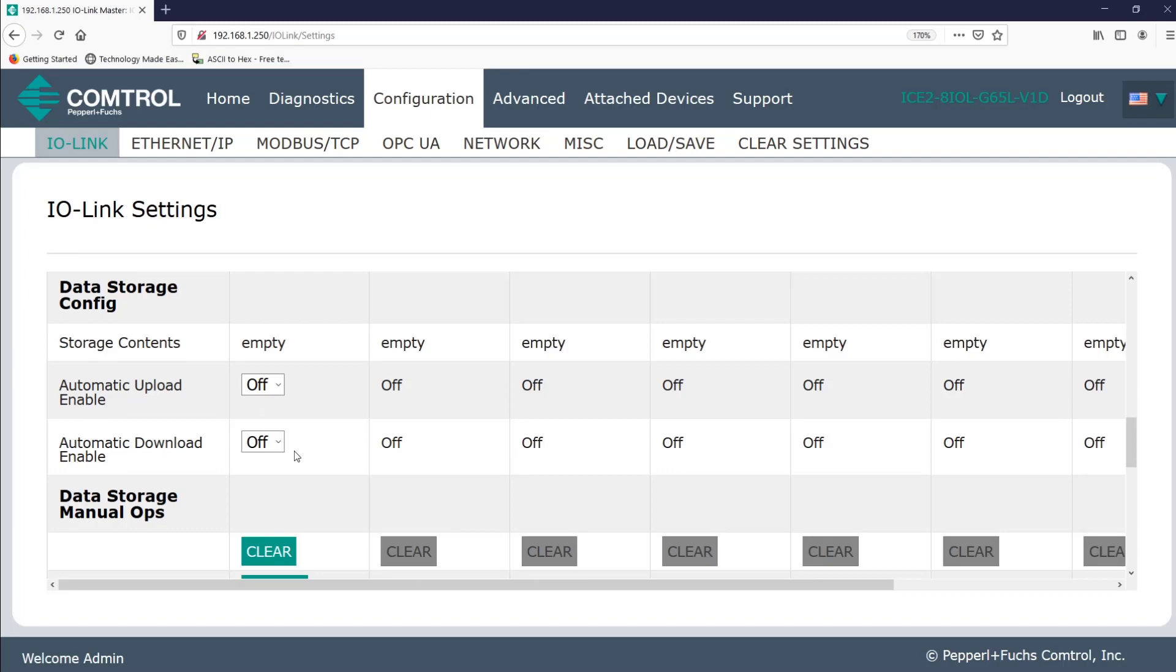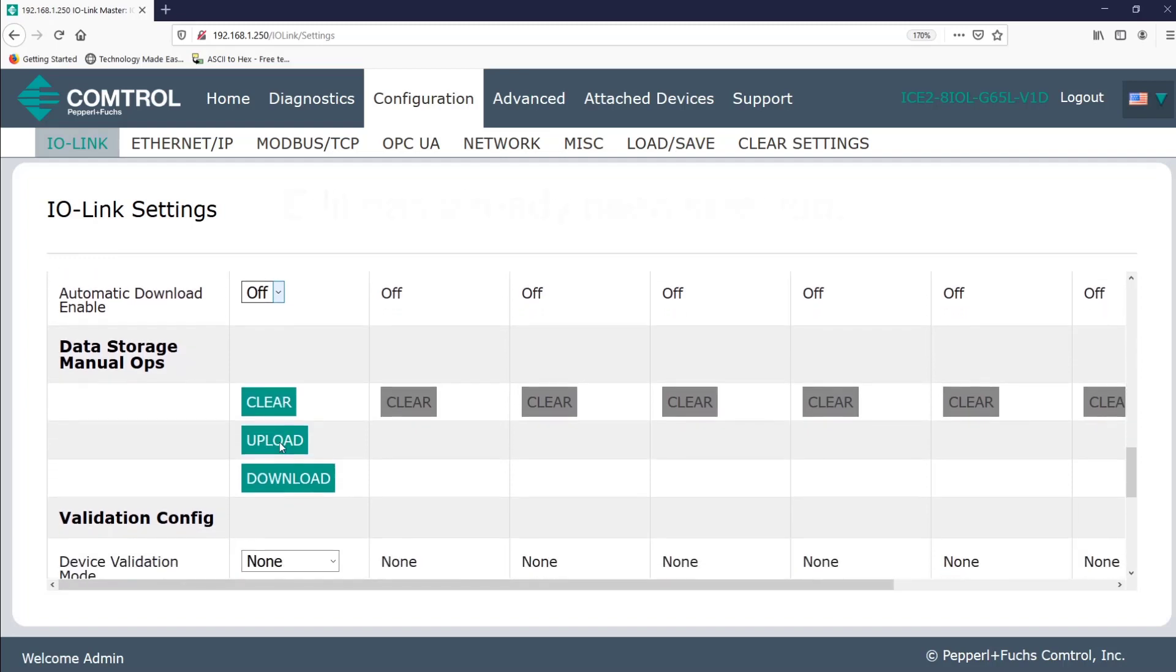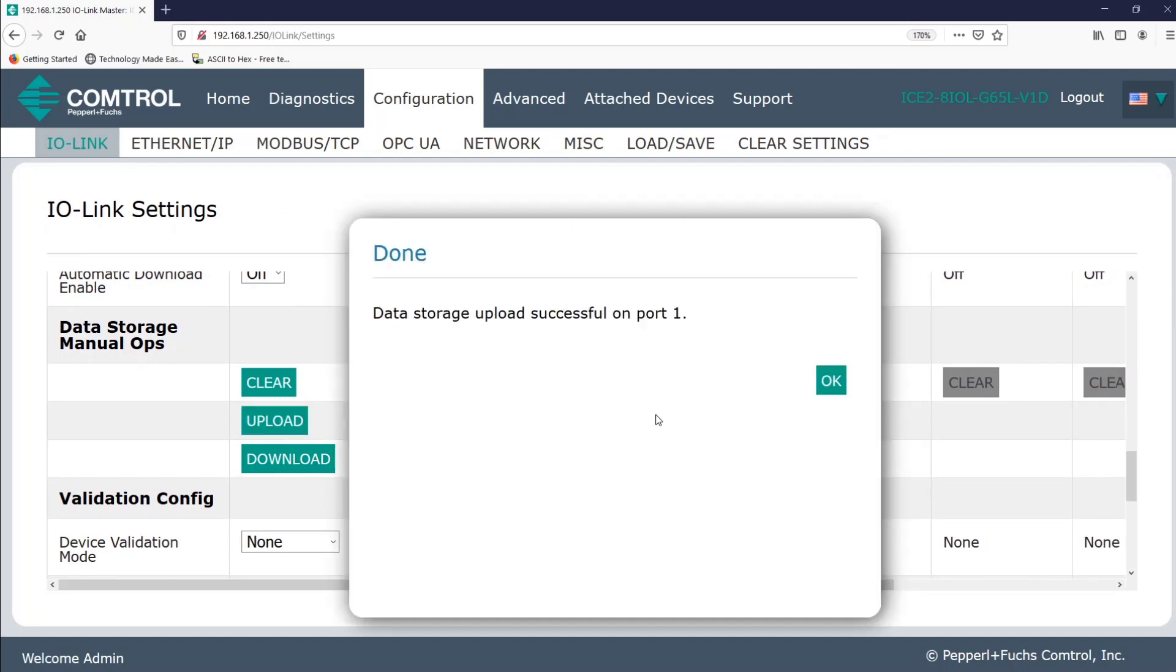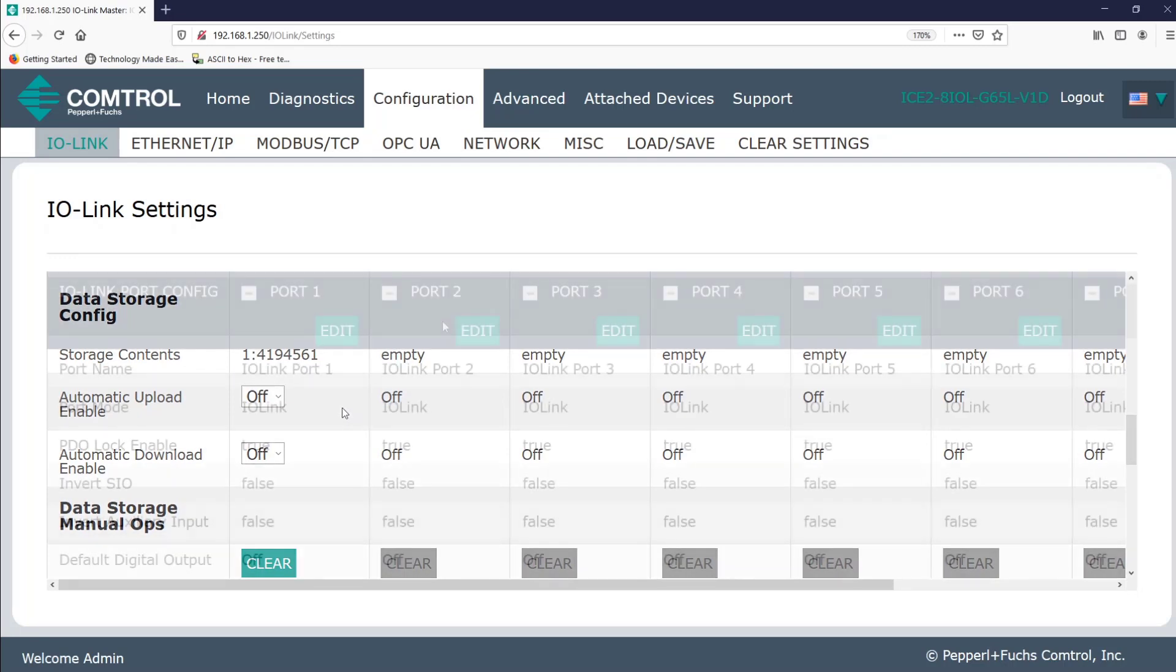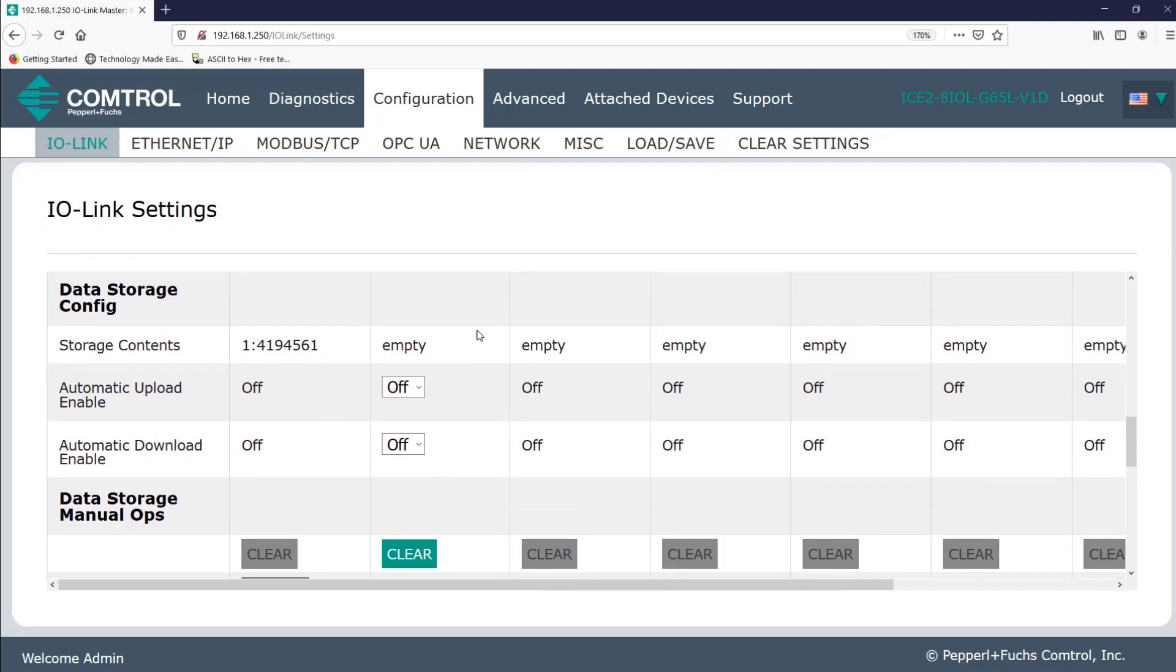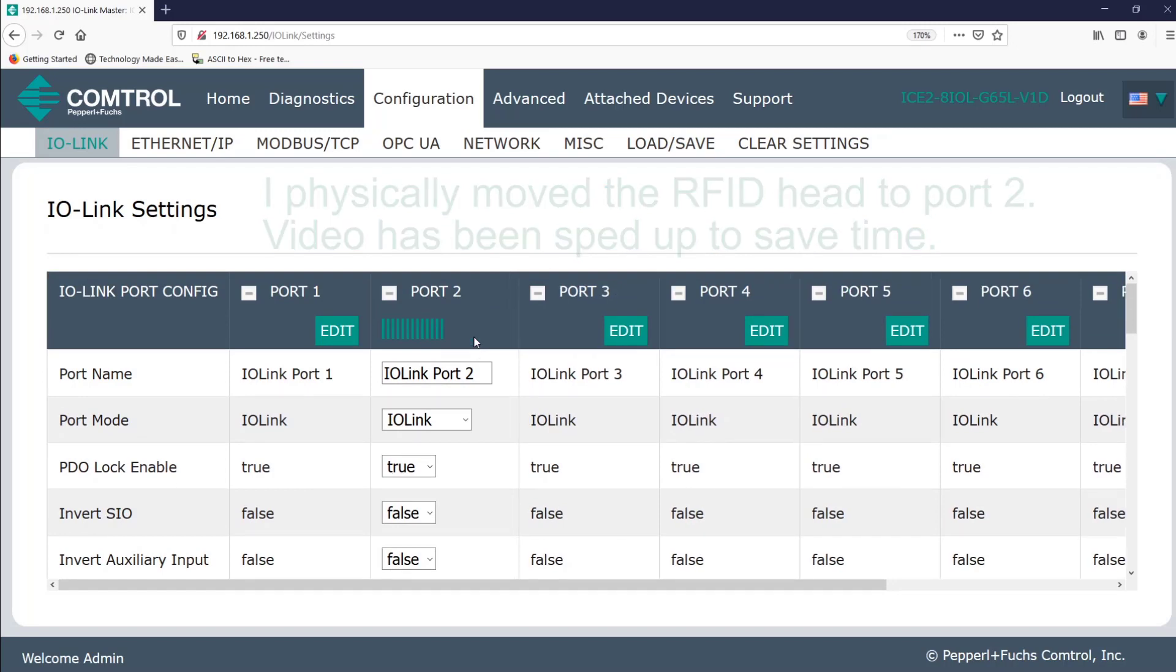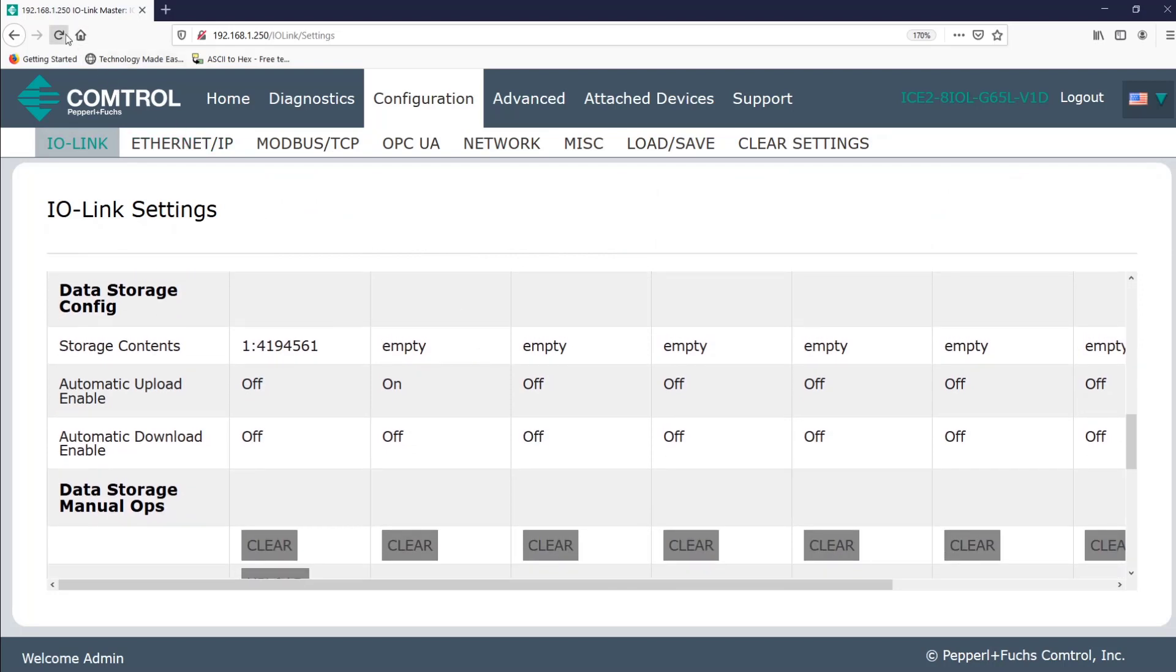You either upload to the IO link master or download to the connected IO link device. The vendor and device IDs do need to match. Automatic uploads and downloads will occur when you adjust device configurations. And yes, there are some small differences between automatic and manual. It'll just depend on your application, which will work best. So for example, my device is already attached to port one. So I'll click edit, then manually upload the device configuration to the ice to IO link master. I'll click continue. And now we can see that the device ID is shown. This helps indicate that the device data has been uploaded to the IO link master. And to show you how to do this automatically, I'll go to port two and click edit. I'll set it up for auto upload. Now watch what happens as I've removed my RFID head from port one and place it onto port two. There is now device data on port two. And once I refresh the screen, it shows that it's been uploaded. Easy as that.